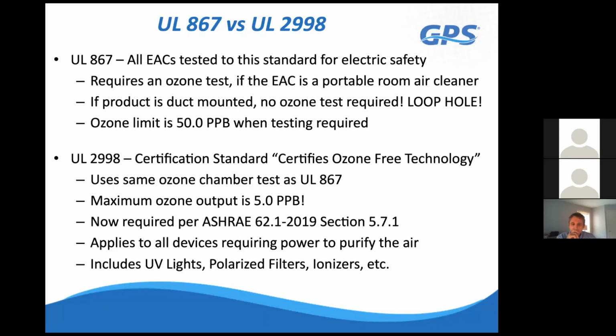So we have a lot of competitors out there in the market that make ionization systems that claim they're ozone free and that they're 867 certified to UL, so all is well, but they don't have the ozone certification because they are duct mounted and they don't have to be tested for it. So ASHRAE said, wait a minute, we've got a problem. We want to make sure that all products are ozone free, whether it's portable units or if it's a duct mounted system, because if you generate ozone in the duct, ozone has a very long half-life, even up to hours. And so if you're generating ozone, it can get to the space where people can breathe it in, and that's what they don't want.